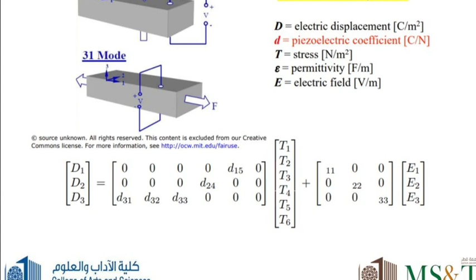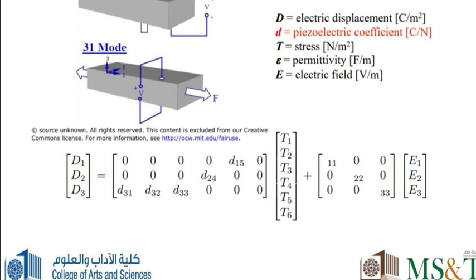That's why we have 3-3 mode and 3-1 mode. When this 3-3 mode operates, the piezoelectric coefficient is calculated based on the force applied and the voltage generated, both in the Z direction, then we call that piezoelectric coefficient the D33 constant.